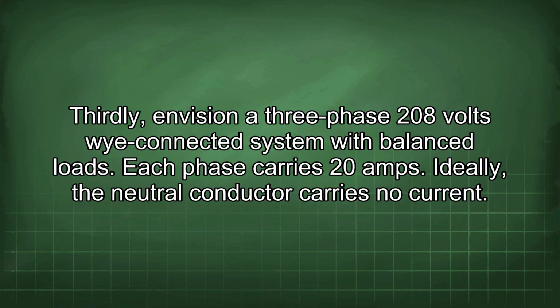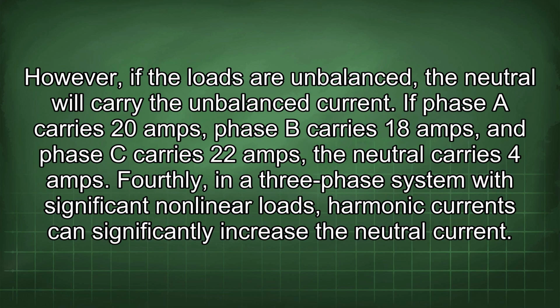Thirdly, envision a 3-phase 208-volt Y-connected system with balanced loads. Each phase carries 20 amps. Ideally, the neutral conductor carries no current. However, if the loads are unbalanced, the neutral will carry the unbalanced current. If phase A carries 20 amps, phase B carries 18 amps, and phase C carries 22 amps, then the neutral carries 4 amps.